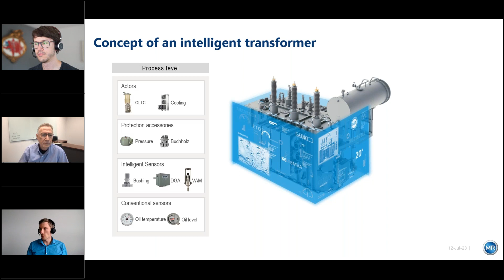Typically we have several layers in the automation system, and the lower level is called the process level. On the process level are all the typical accessories on power transformers, like conventional sensors—every transformer has oil temperature sensors, oil level indicators—then you might have intelligent sensors like a bushing monitor or a DGA sensor.